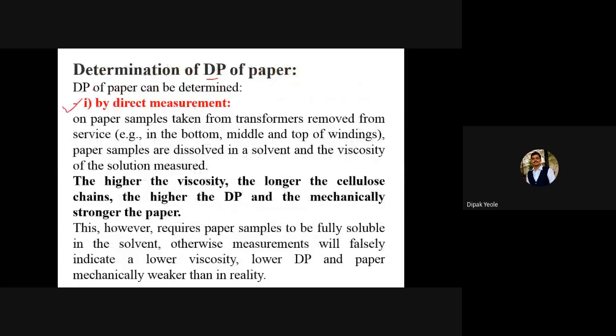Now we are interested in the first measurement, which is called direct measurement. The name indicates itself, we have to use direct measurement. In this, let's take paper samples. Paper sample means we have to take out the paper sample from the transformer removed from service. From the transformer we are using for our application, we have to remove the insulation paper.